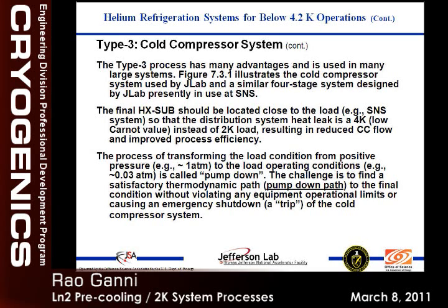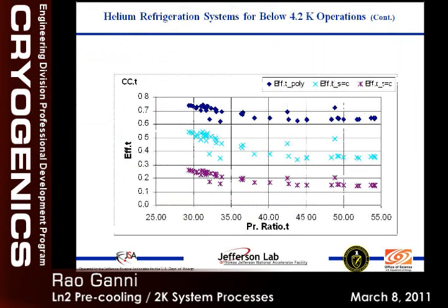appropriately. The disadvantage of this is that because these compressors are in series and the pressure ratio is too high, establishing the pump down path took us quite a while initially, as I outlined at the beginning. Once we figured it out, we are not as concerned as we used to be. Figuring out the pump down path itself is a science.